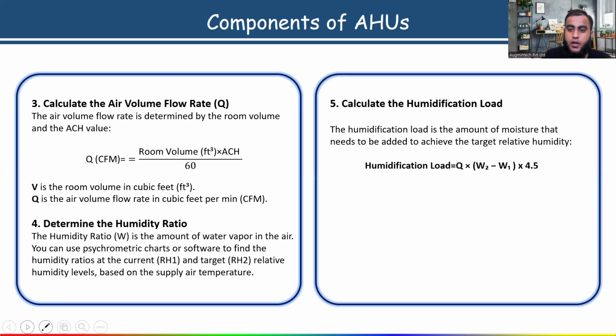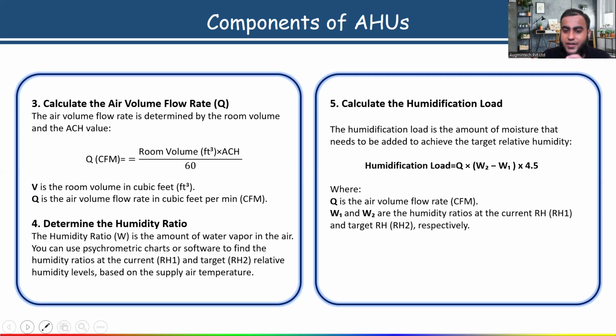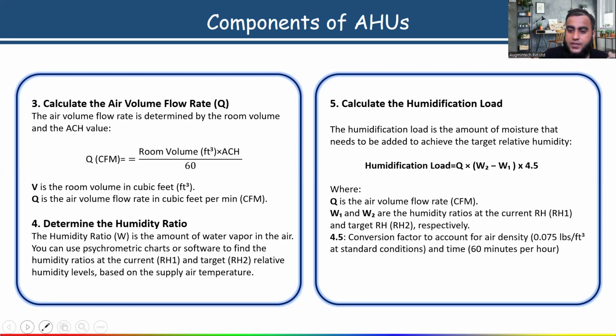See, the formula is simple. Humidification load is equal to Q, means airflow rate, which we have already calculated, into W2 minus W1. What is this? Same. Q is the volume airflow rate. W1 and W2 are the humidity ratio at the current and target relative humidity respectively. And the 4.5 factor, what is it? It is the conversion factor to account for air density and time. Okay. So remember 4.5. So this is the formula which we have to use.